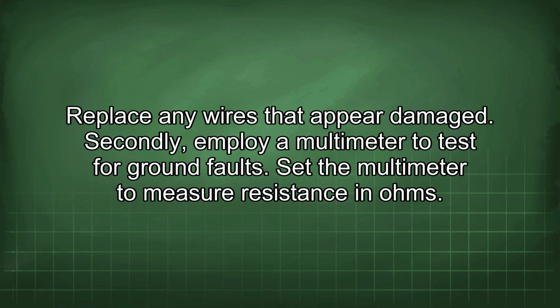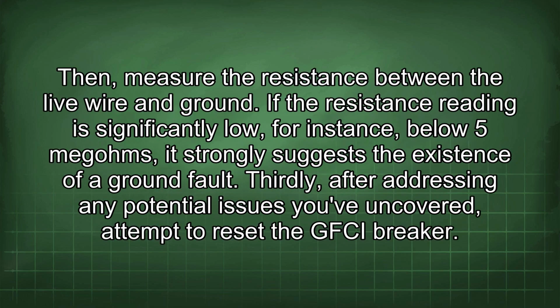Secondly, employ a multimeter to test for ground faults. Set the multimeter to measure resistance in ohms. Then, measure the resistance between the live wire and ground. If the resistance reading is significantly low, for instance below 5 megohms, it strongly suggests the existence of a ground fault. Thirdly, after addressing any potential issues you've uncovered, attempt to reset the GFCI breaker.